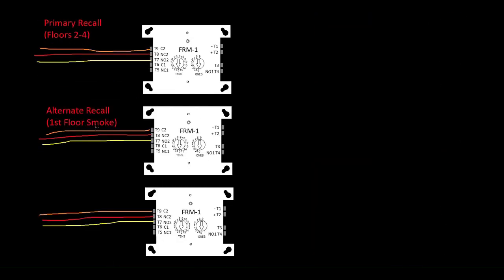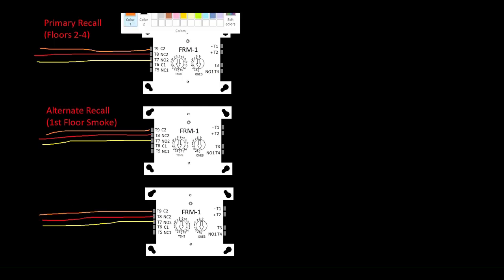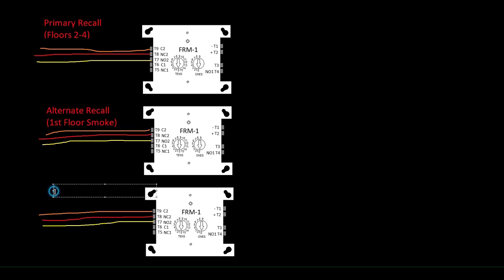In that case, you would have your primary recall, which is when no fire hat is required, you'd have your alternate recall, which we would then label first floor smoke, and then instead of having a fire hat relay, you would have something like a relay that simply says top of shaft.